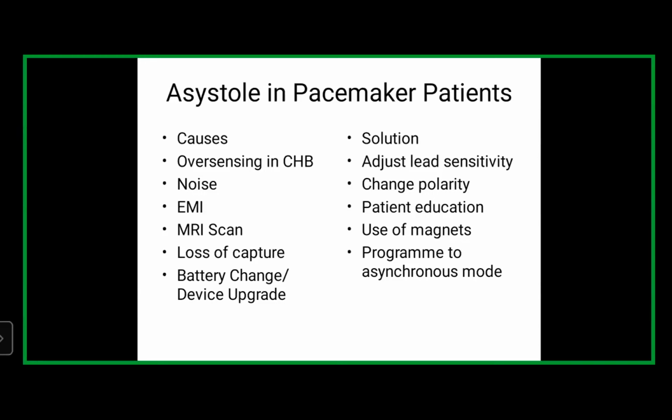troubleshooting will require checking the sense polarity, whether it's unipolar or bipolar. Unipolar sense polarity is usually susceptible to oversensing because of far-field channel interference from the myocardium and all of that. But bipolar is preferable, and current technology gives us the opportunity to go straight to bipolar.